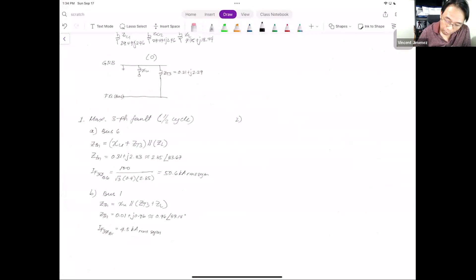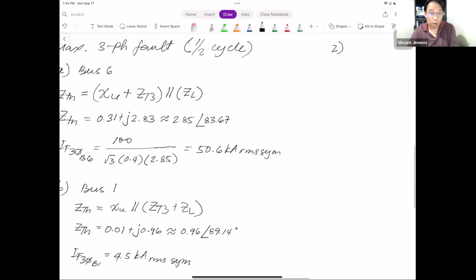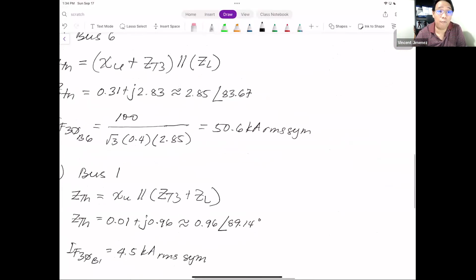Objective number 2, minimum three-phase fault. By the way, this will apply multiplying factors per IEEE standard. The X over R ratio will be used there. You will need to multiply it by a multiplying factor, which will then be the basis for selecting the device. We'll do that later. Let's finish this objective number 2 first, the minimum three-phase fault.